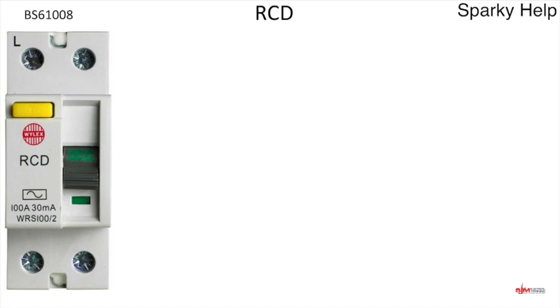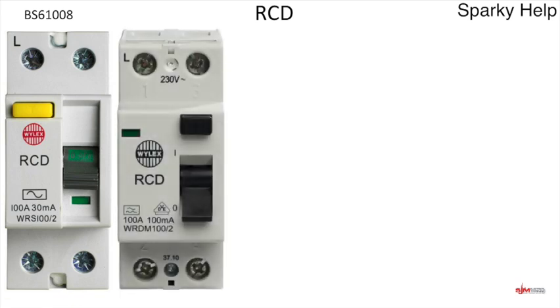This particular one, by this manufacturer, is a 100A RCD. RCDs only pick up on earth faults, or an imbalance between the line and neutral. This one is 30mA and has this symbol on the front, which basically means it's an AC type — very common, but probably not going to be used as time goes on. It will most likely be replaced by this Type A RCD. This one is also 100A but at 100mA.